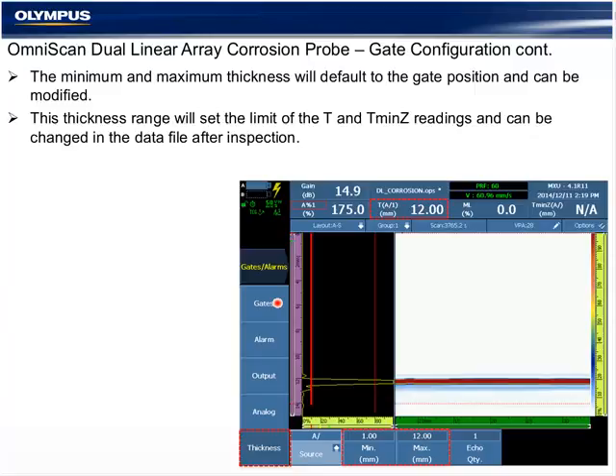Under the gate menu, we also adjust the thickness. This is a function designed for corrosion monitoring, and this allows selection of the source if you needed to change to include a B gate minus A gate to remove a paint coating, or if you had an application where you needed peak readings instead of leading edge, it could be adjusted here for the source of the reading, which will also be the source of the output for the C-scan data to third-party software.